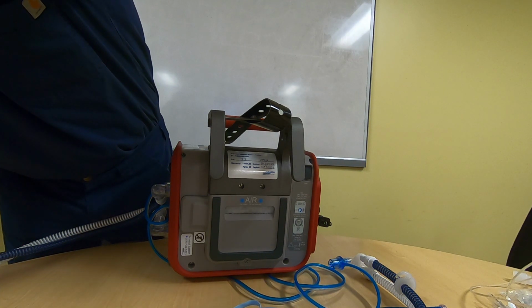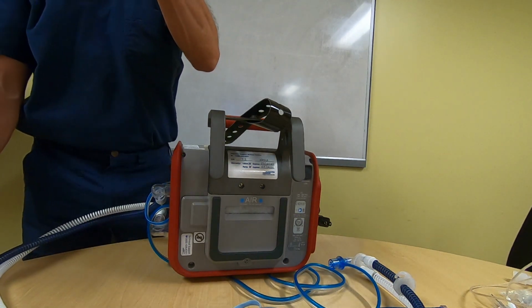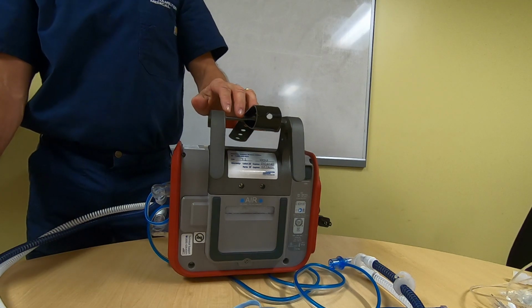So this gas is mixed inspiratory and expiratory gas. The sample line should always be on the inspiratory side. Oh, I see what you're saying. Yeah, you're right, so it's going to be a little off.